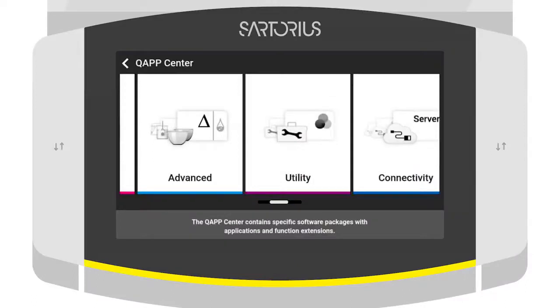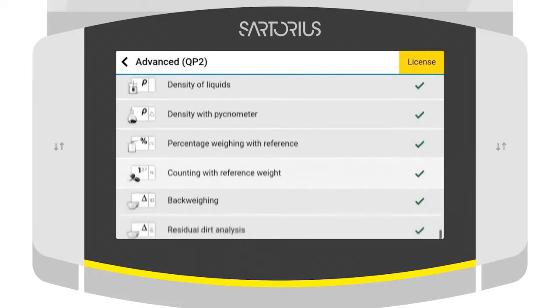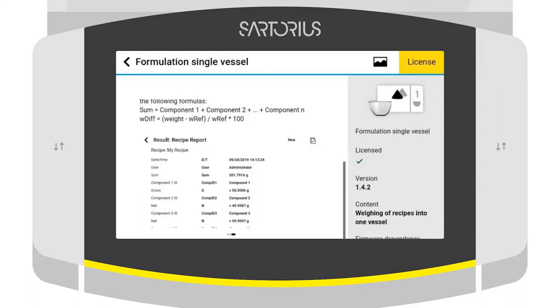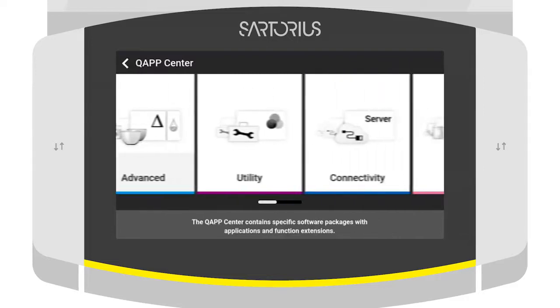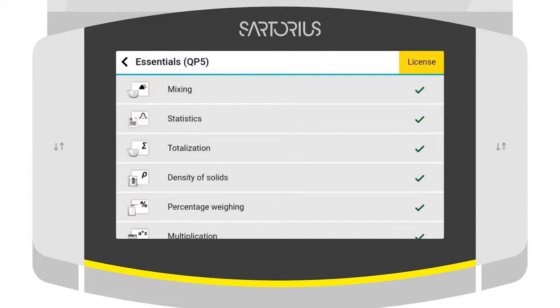Through the use of Q-Apps — small applications for different weighing methods that run on the balance — the efficiency and safety of your workflow can be increased, ensuring that your SOP is followed. Cubis II comes with more than 50 Q-Apps for typical weighing workflows and offers the possibility to create customized workflows that fit 100%.